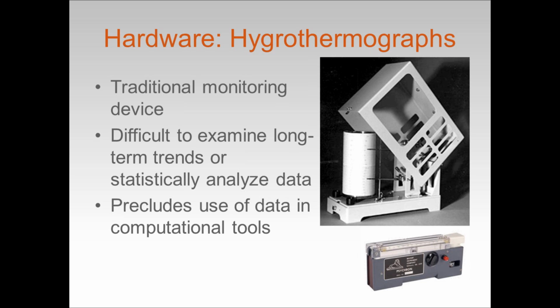Okay. A step up from the hygrometer is the hygrothermograph, which I assume most of you are familiar with. We've been seeing these for decades. "Why can't I continue to use my hygrothermograph?" is something I used to hear from people a lot. And the short answer is that you can. Hygrothermographs remain available, and providing that they're properly cared for, they can provide you with years of yeoman service with relatively little effort. They do need to be calibrated regularly, meaning weekly or monthly, depending on when you change the paper charts, because the horsehair, that is the measurement for the relative humidity, moves out of calibration relatively quickly.